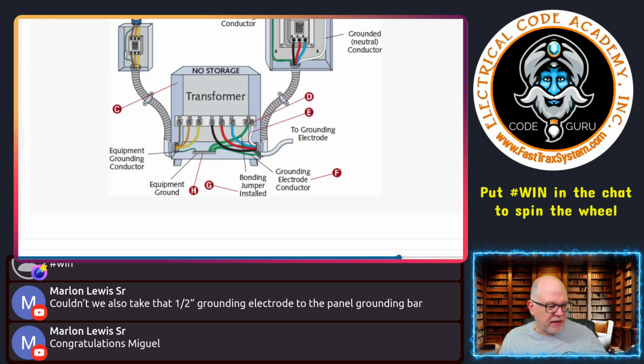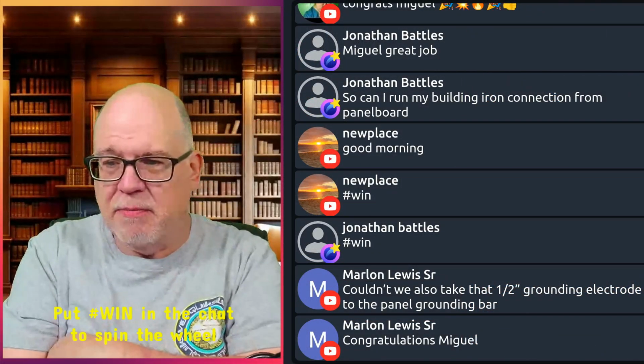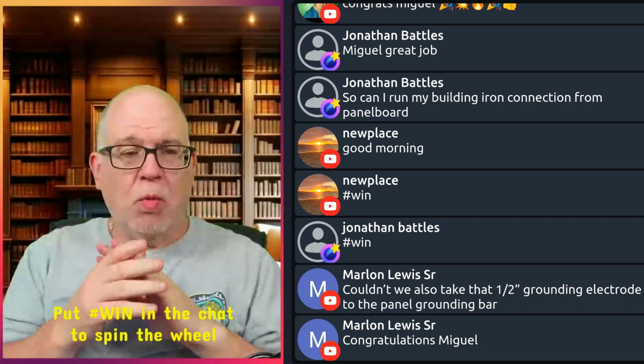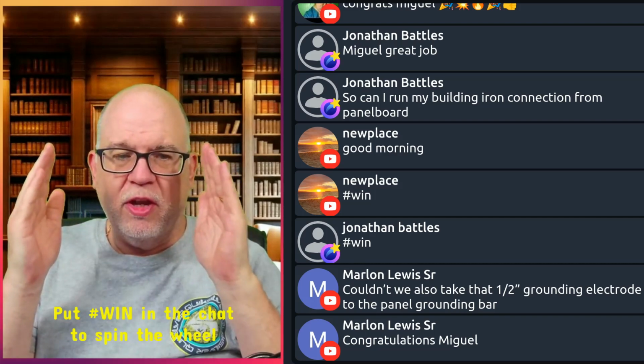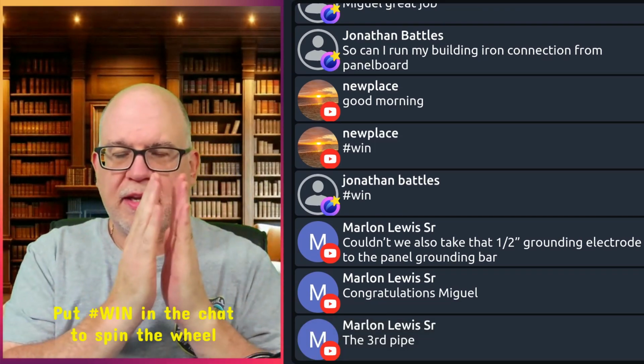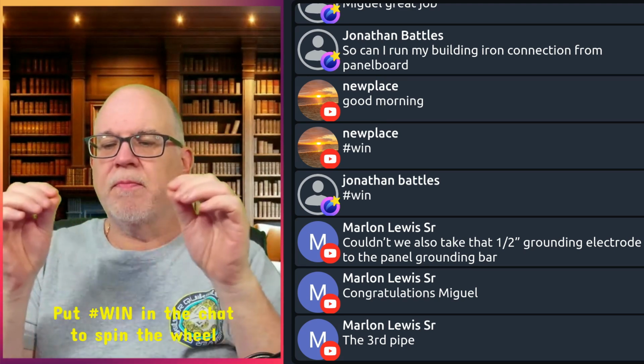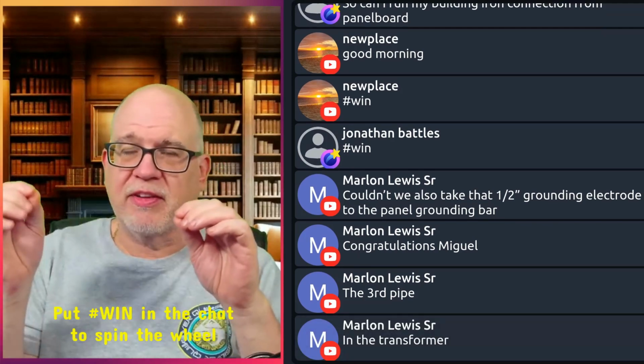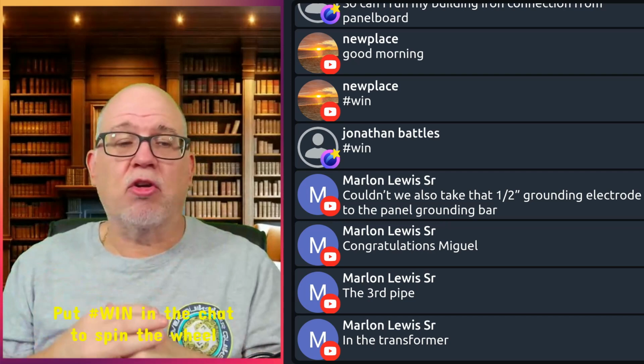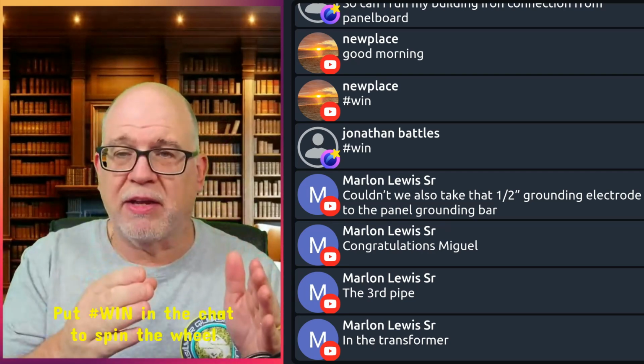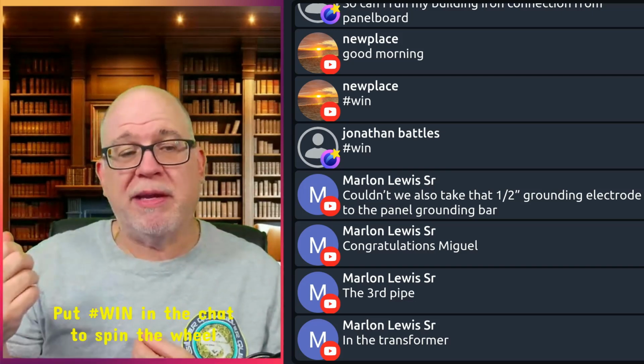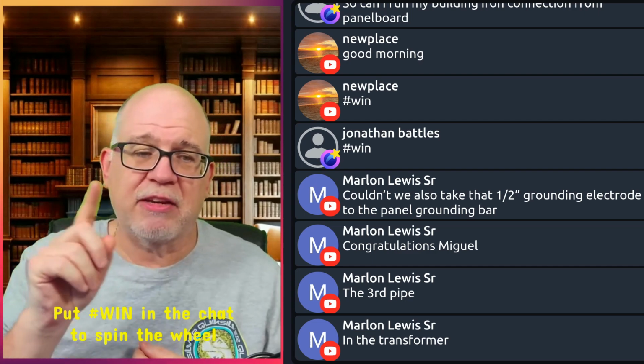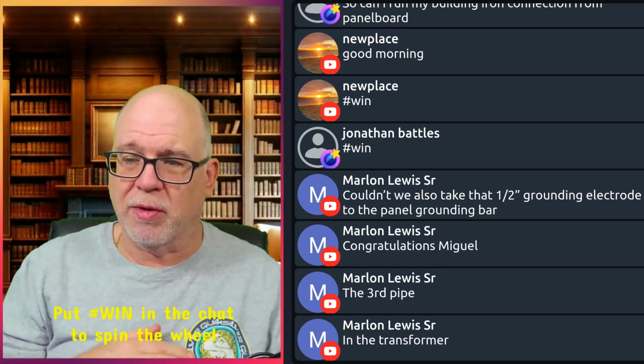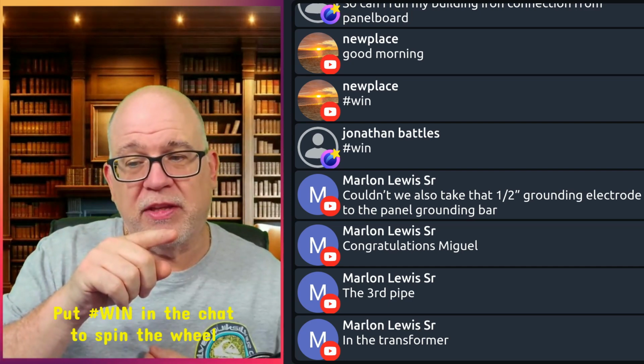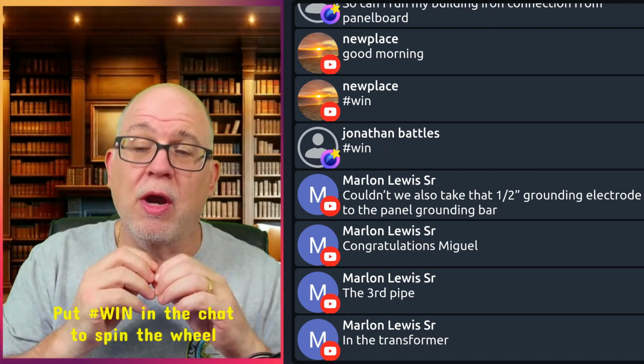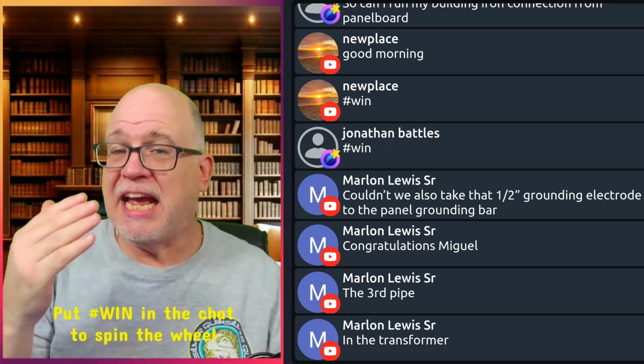Why is that important? The reason that's important is that in a panel, people ask all the time about making connections. I've shown you some panels before where my neutral bus and my equipment grounding bus are tied together with a wire. They're not all on one connection. They're connected together with a wire, that is my main bonding jumper, let's say, in a panel. So I can take my grounding electrode conductor, which typically has to connect to the XO bus, but I am permitted to connect it to the equipment grounding terminal bus only, provided that bonding jumper is sized properly. And so it's the same in a panel as it is in the transformer. So that grounding electrode conductor can actually connect to the equipment grounding terminal bus rather than the XO, because that is a wire type system bonding jumper and it was sized properly.